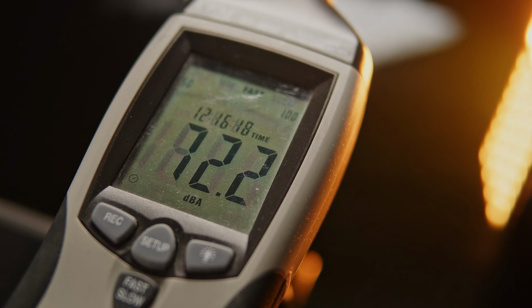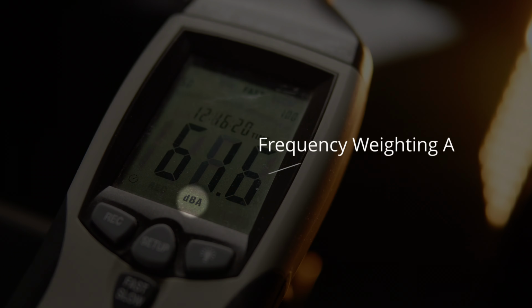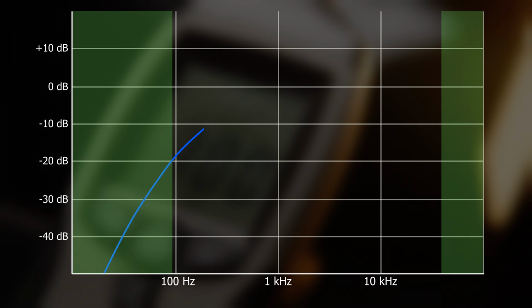One of the factors is frequency weighting. Notice the units on the display. A after decibels means that the meter is not treating all the frequencies equally. Some parts of the sound spectrum are suppressed and don't influence the measurement as much as others.